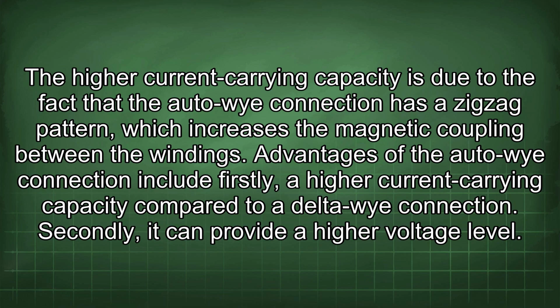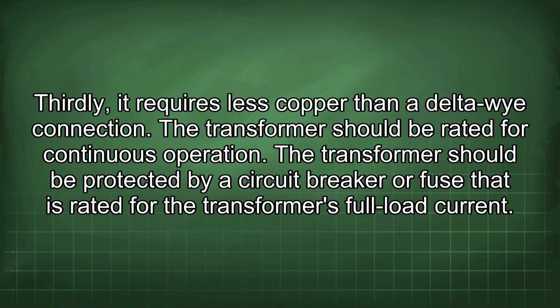Advantages of the Auto-Wye connection include firstly, a higher current carrying capacity compared to a Delta-Wye connection. Secondly, it can provide a higher voltage level. Thirdly, it requires less copper than a Delta-Wye connection. The transformer should be rated for continuous operation. The transformer should be protected by a circuit breaker or fuse that is rated for the transformer's full load current.